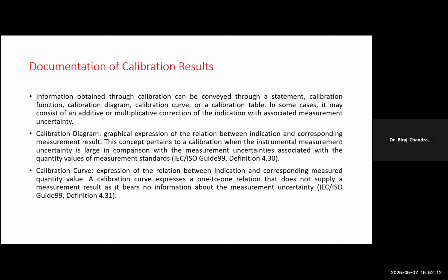It can be whatever information is obtained through calibration. So whenever we visit any healthcare organization, we may ask them to show the calibration certificate. The calibration certificates can be represented in two formats, that is calibration diagram or calibration curve. A calibration diagram is a graphical expression of the relation between indication and corresponding measurement results. And the curve is an expression of the relation between indication and corresponding measured quantity value. A calibration curve expresses a one-to-one relation that does not supply a measurement result, as it bears no information about the measurement uncertainty.